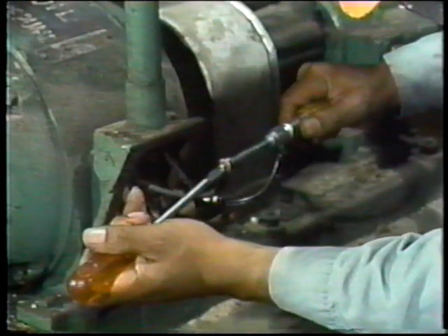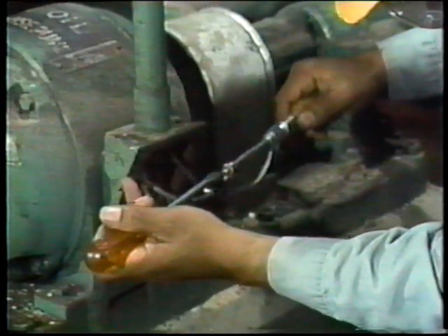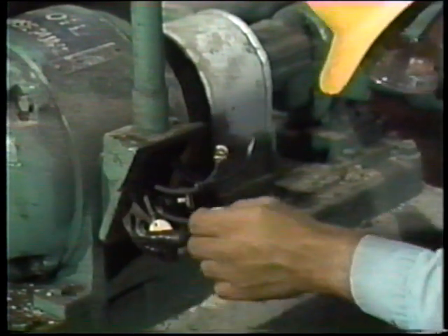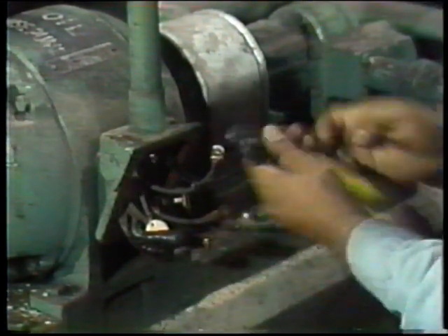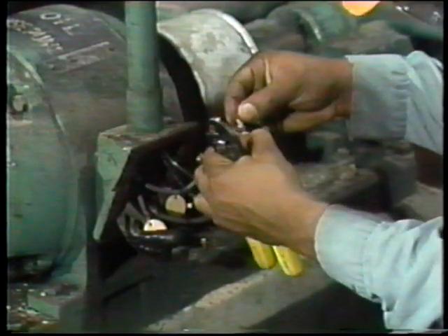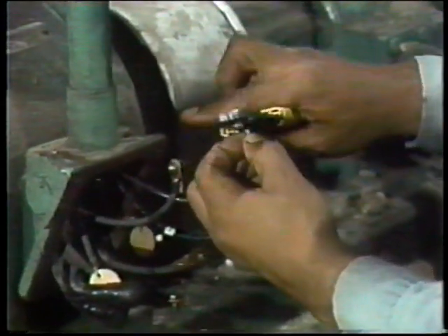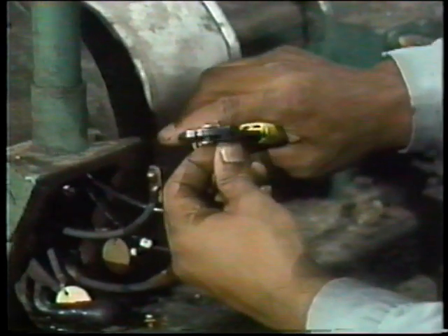Now let's go back to the plant and watch Bill as he does some terminations. He's already completed the first mechanical connection. We'll pick it up as he starts the second. The type of terminator he uses is a lug. He holds the lug up to the conductor to judge how much insulation should be stripped away. Then he strips it.